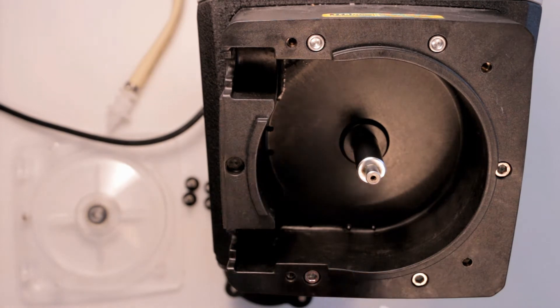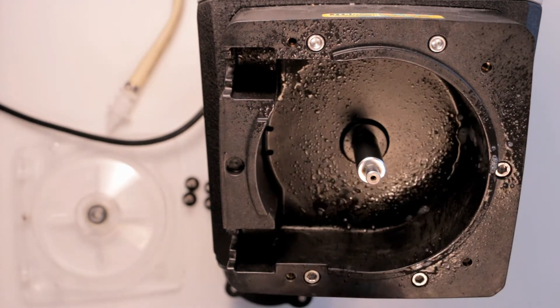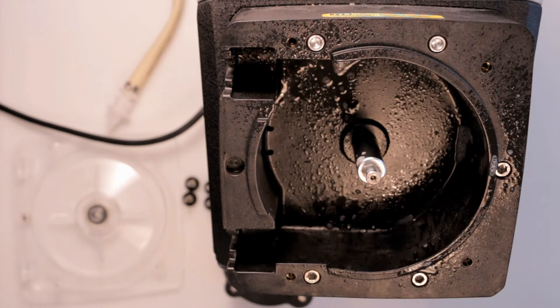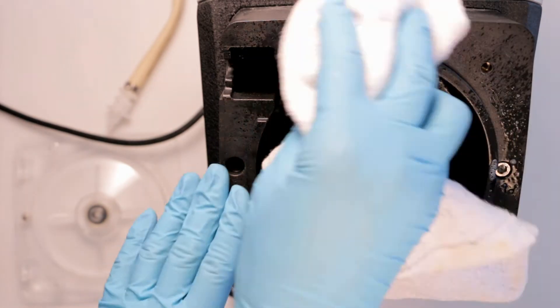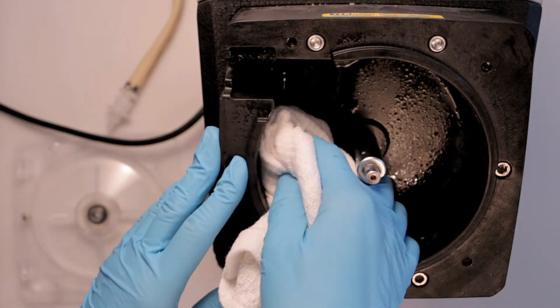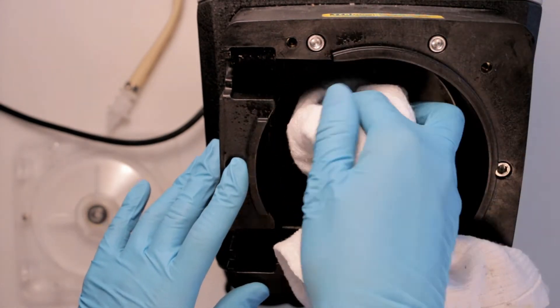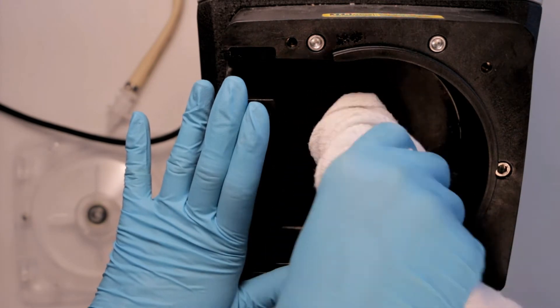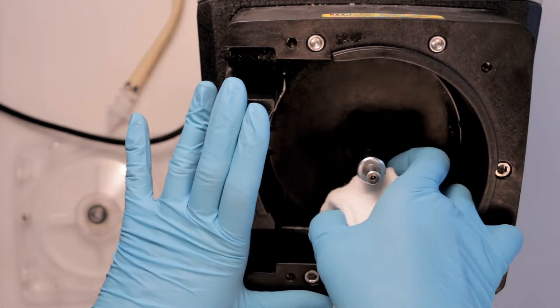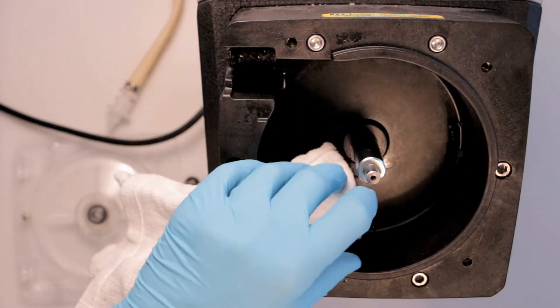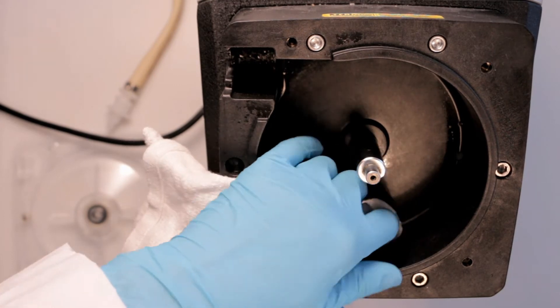Wipe chemical, grease, and debris from the interior of the pump head and motor shaft with the degreaser and rag. Be sure the TFD sensor pins are also intact and clear of debris. They're located at the bottom back of the pump head.